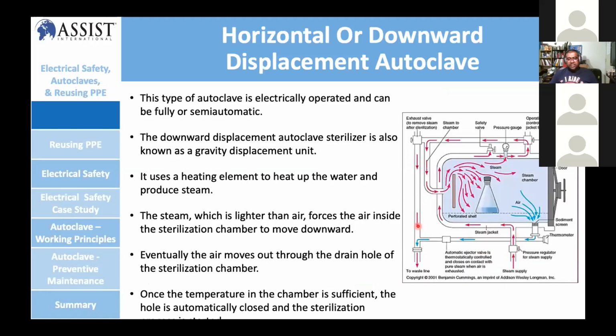Electrically operated autoclaves come fully automated and semi-automated, depending on the brand and the model you are buying. So these are downward displacement autoclaves, or gravity displacement units. You can see how the method is done. Using the heating element and water, you produce the steam, and the steam, which is lighter than air, is forced into the sterilizing chamber and moves downward. You can see the blue one moving downward. Then eventually the air moves out through the drain. The red one is where the steam goes in and sterilizes this chamber, and it moves towards the bottom and goes out.